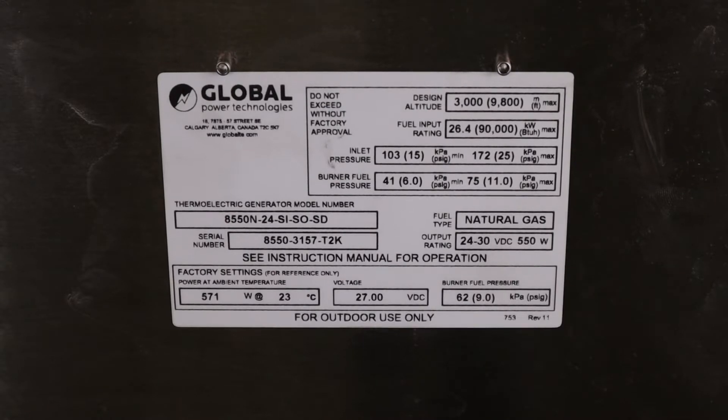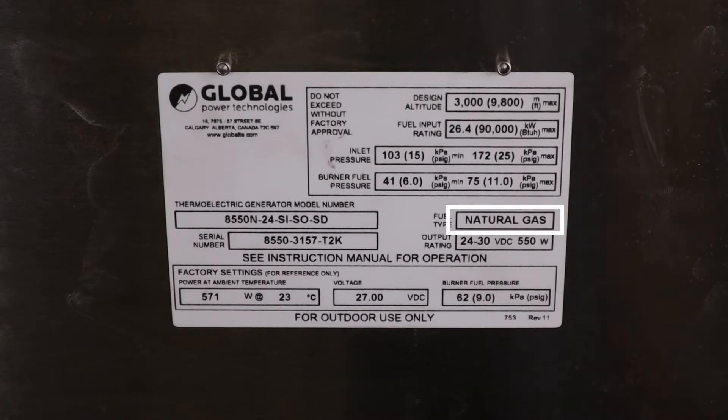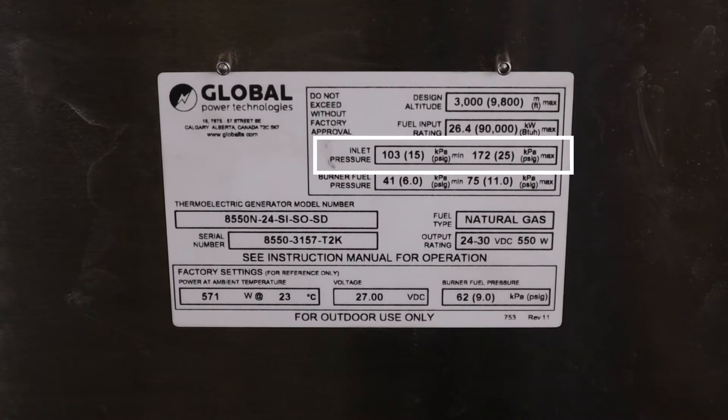The fuel pressure supplied may need to be adjusted for altitude. Figure 7 in the manual shows the correction for variation from the factory altitude of 750 meters or 2,460 feet. Be sure to use only the type of fuel indicated on the data plate. The maximum inlet fuel pressure must never exceed 172 kPa or 25 psi.